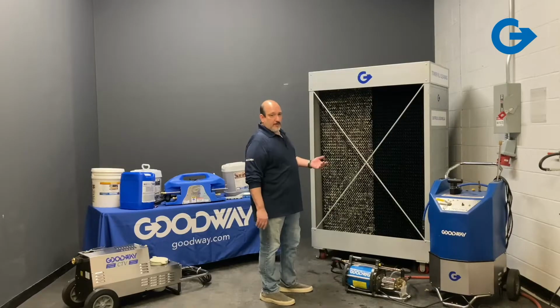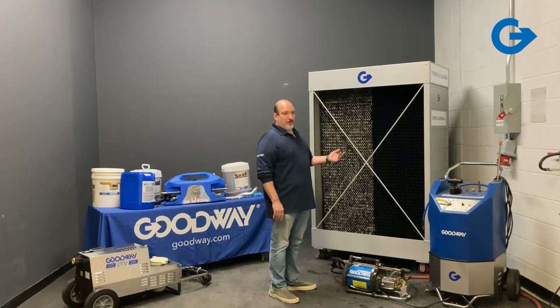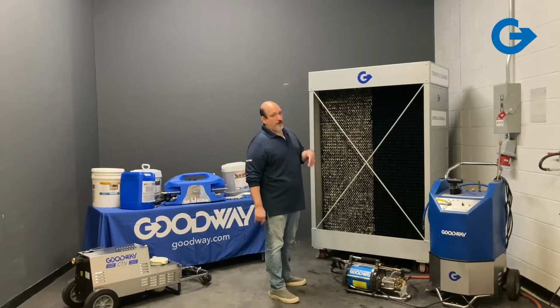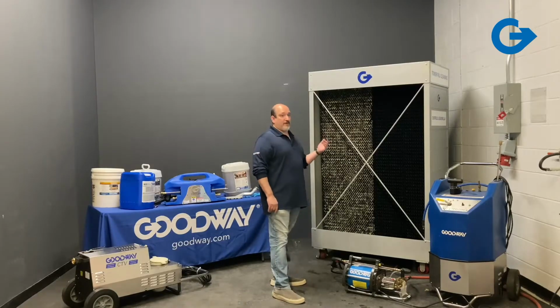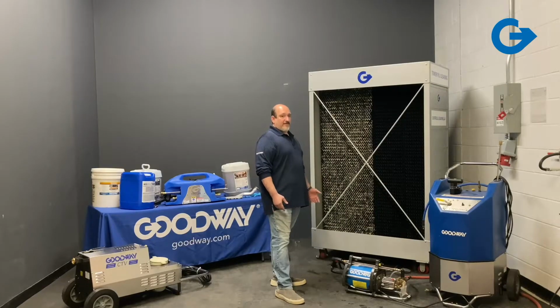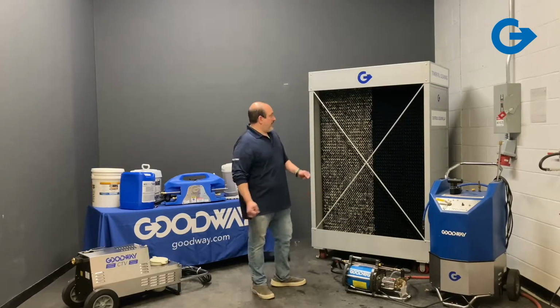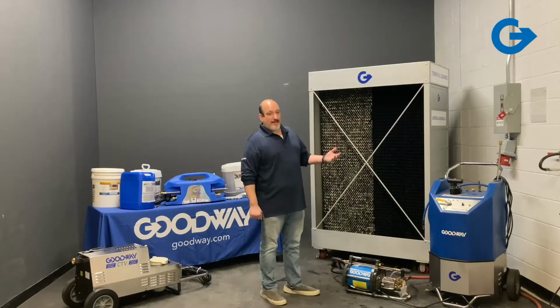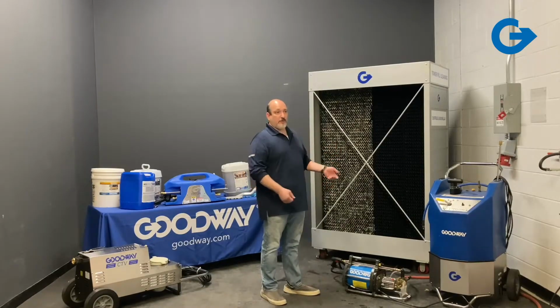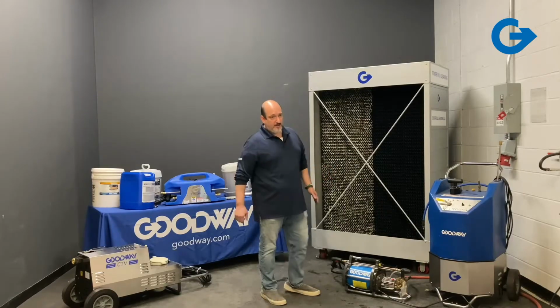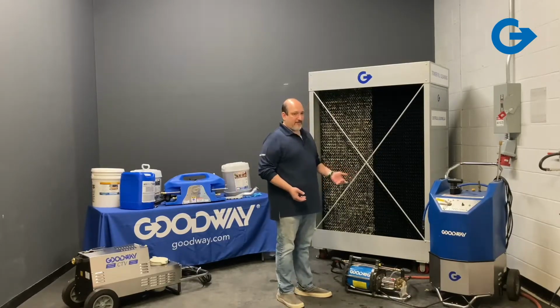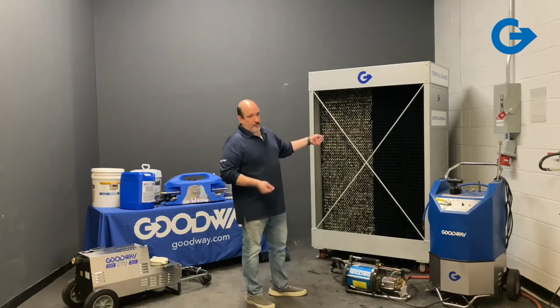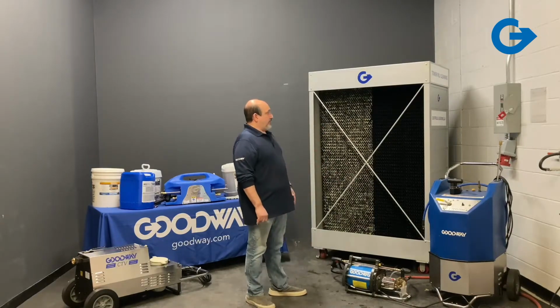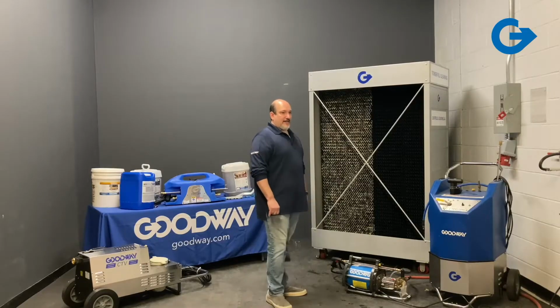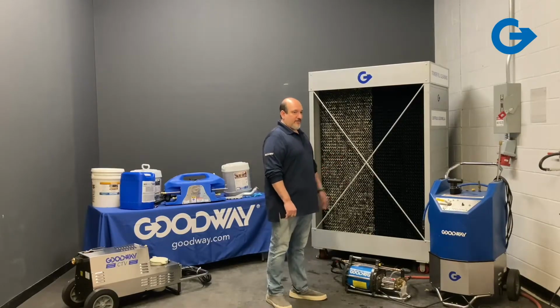We've been making equipment for cleaning chillers for a long time. That's kind of what we're known for, tube cleaning equipment. And we frequently get asked over the years, what do you have for cleaning out the cooling towers? In the past, people would just get a pressure washer and blast it down, maybe spend a weekend draining the whole tower down, going in with shovels and vacuums and drums trying to get all the mud and sediment out of the basin, while another person uses a pressure washer to try and clean the fill. What we found is it's not really an efficient way to clean it, and it's not getting the end result they want either.